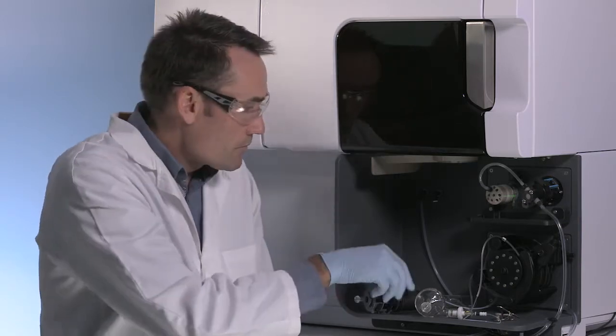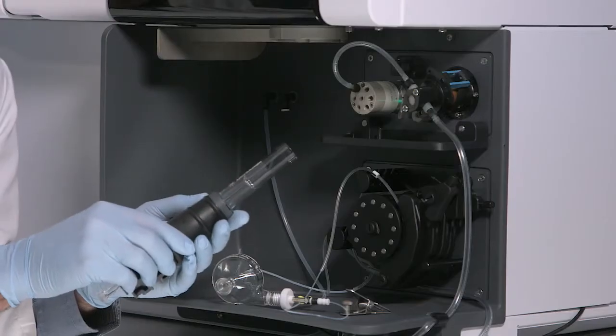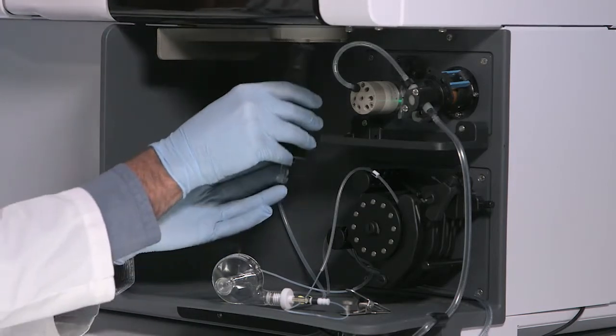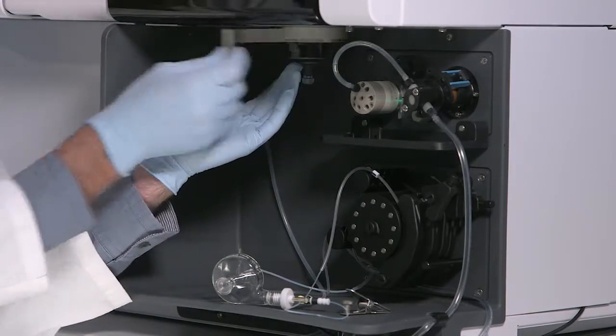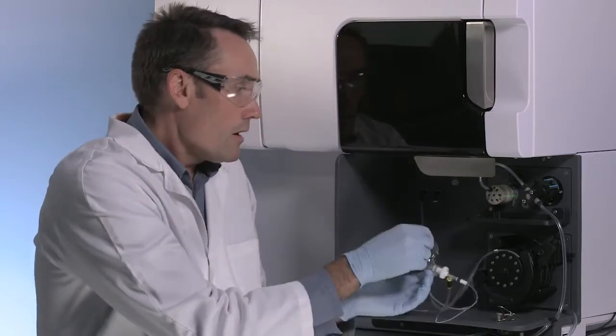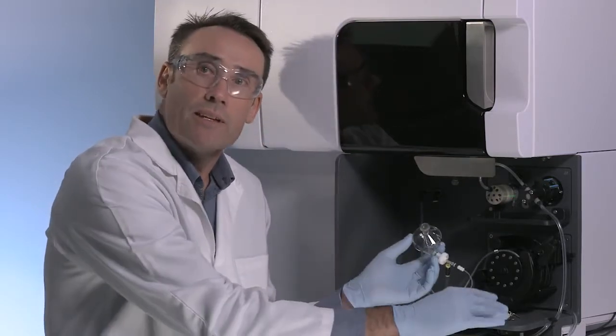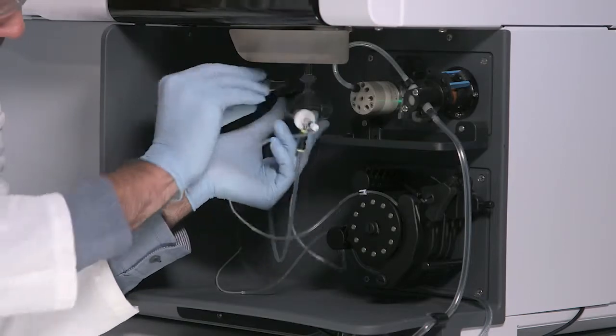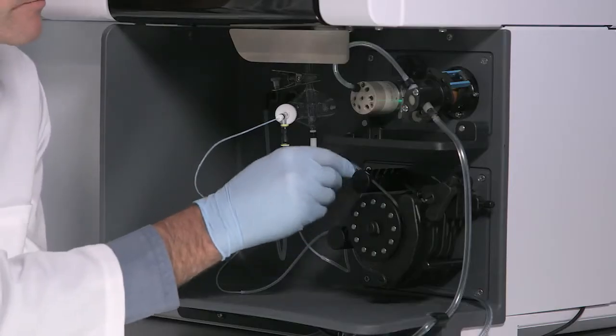So here we are in front of the new 5110 ICP OES. Ross, can you walk us through the setup of the instrument? Setting up the sample introduction components for a typical aqueous analysis is very simple. We insert the torch, we connect the spray chamber and nebulizer assembly, we clamp the pump tube.